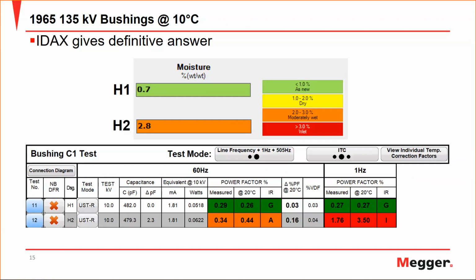Now, what we have found mainly in high voltage bushings has usually not been issues with moisture, but issues with contamination and degradation of the solid insulation due to overheating, due to transients in the system that have affected the insulation condition, due to faults in the system that have affected the insulation condition. So let's keep this in mind.